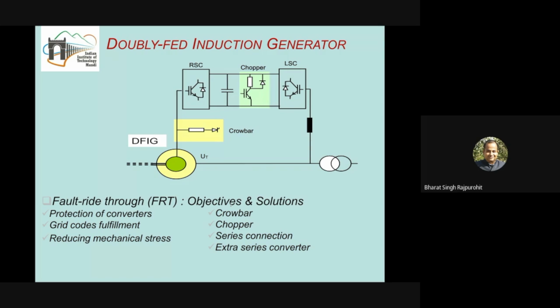As soon as the crowbar comes into operation, it will close the rotor circuit of the doubly-fed induction generator by a resistance, and this resistance is able to dissipate the extra amount of energy. So now you are able to see that when a crowbar is operational, the DFIG becomes a simple wound rotor induction generator with the rotor short circuited by these resistances.